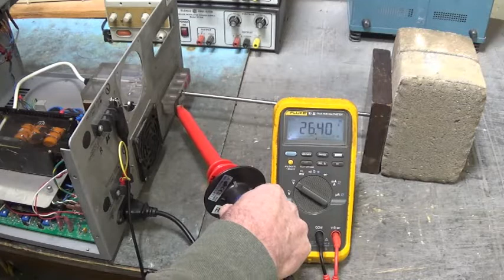Oh yeah, we're starting to arc over. Did you hear that? We're ionizing the air now. Okay. Oh, I smell it too. There's 25, 26 kilovolts on the Charge Master meter, and we have 26.4 kilovolts DC on the Fluke voltmeter. Let's try to go a little bit higher. Oh, you hear that? We're arcing over. We don't have good contact between that rod and the output of the Charge Master. I'm going to turn it down. Did you see the sparks right there? Oh, imagine that. Okay. We took it up to 26,000 volts. 4,000 volts more, we would have made it to 30. But I'm going to call that good.